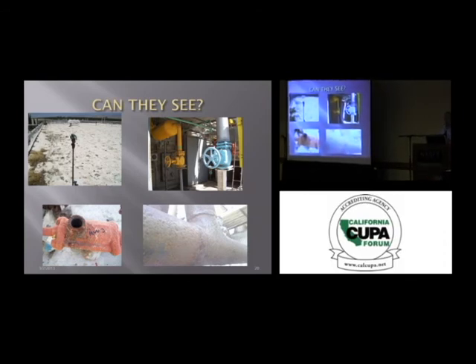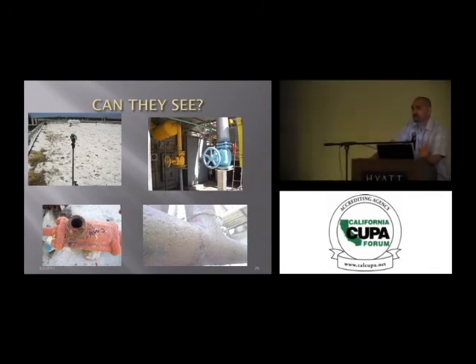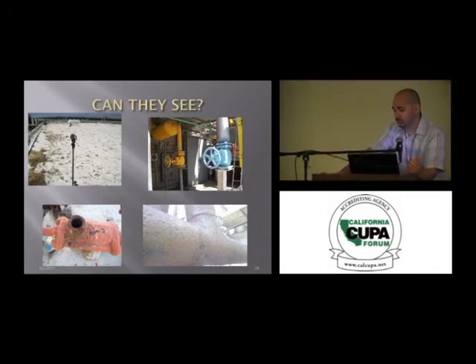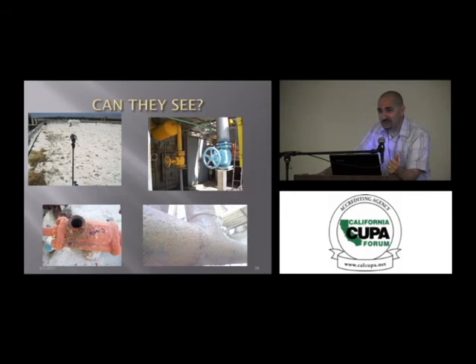So the picture to the right-hand side, what's the issue there? There used to be a compressor sitting there. You got the high stage discharge and you got the suction side. The isolation valve groups. There's no flange, and the system is operating. There's about 4 compressors right next to it. The condensers, there's 2 condensers right next to them, and you just go over there and you crack that valve open, you're releasing ammonia.